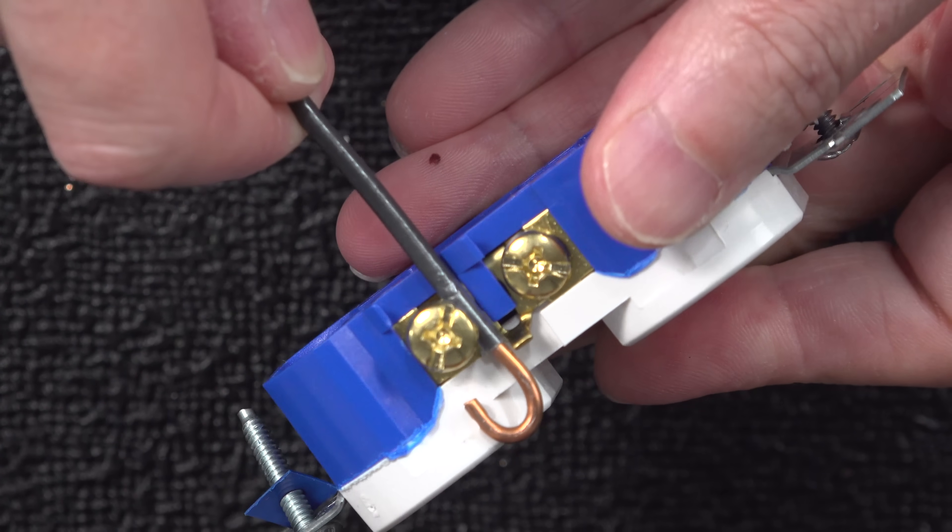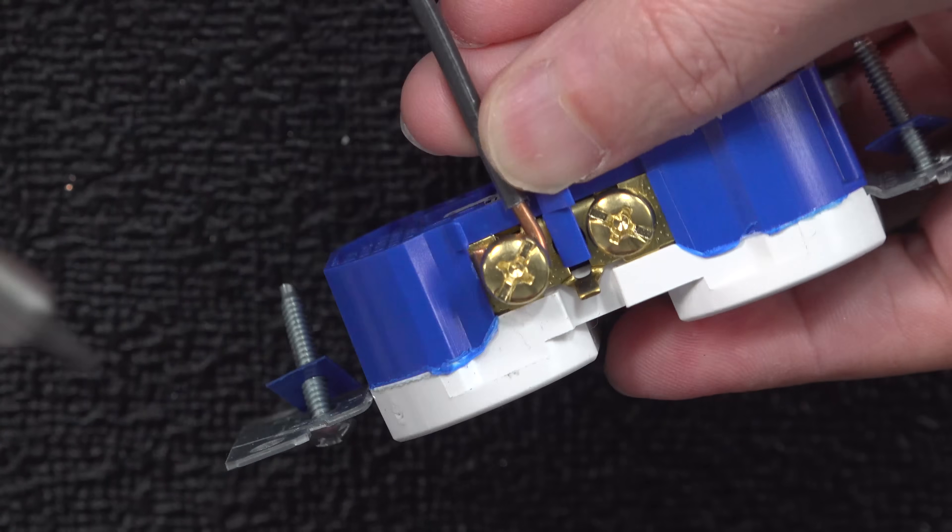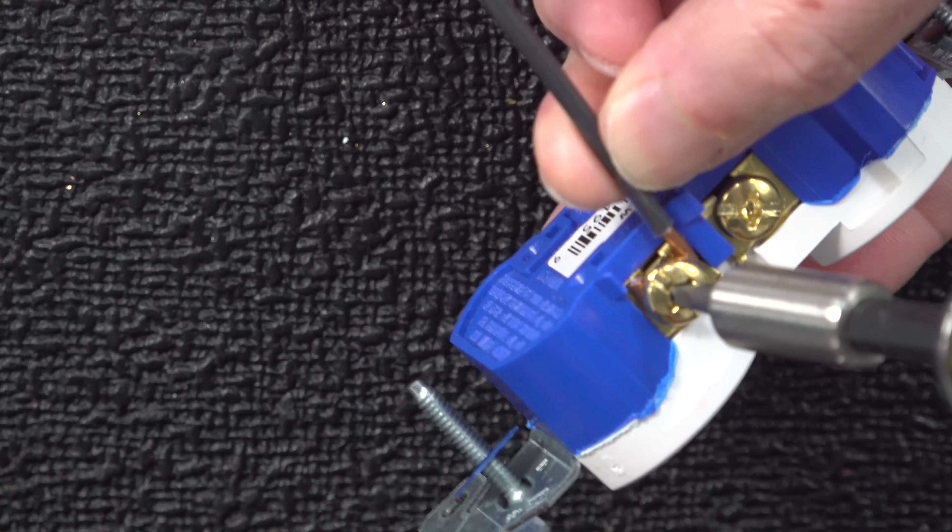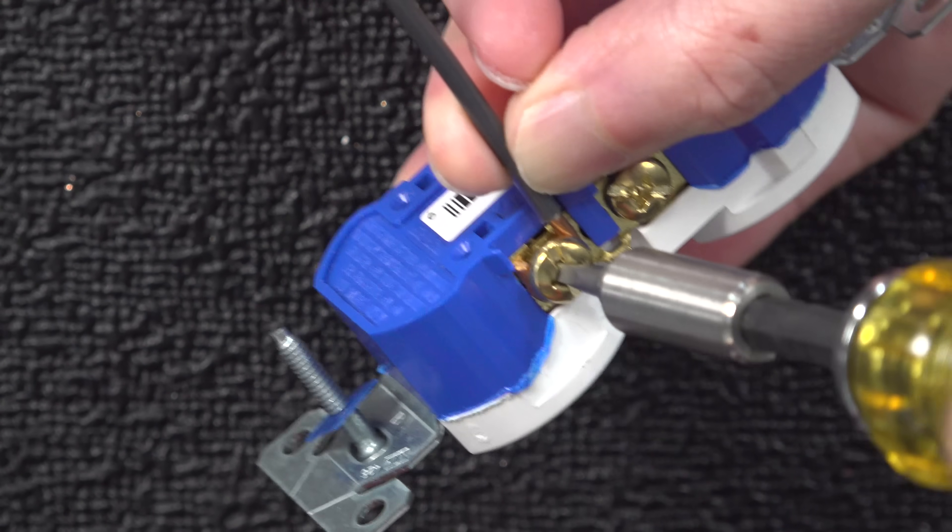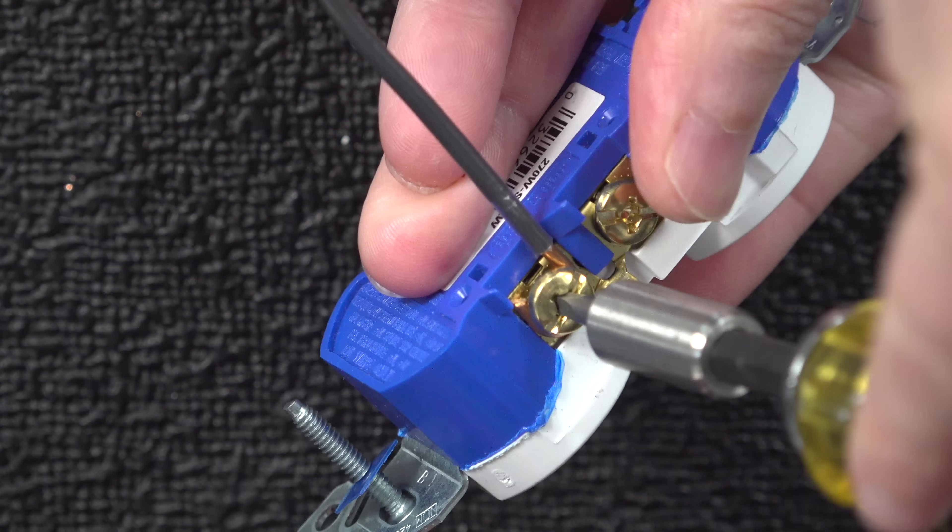The correct amount of insulation you want to remove is three quarters of an inch if you're going to be making a hook. Once you do that, you'll be able to form a hook that's going to fit properly. You won't have too much wire sticking out the end and you won't have too little so that you get any insulation underneath that screw.